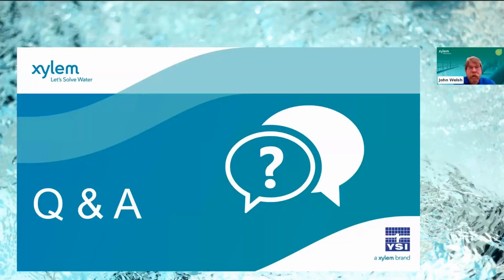We do recommend, however, a yearly PM, and as was the case with its predecessor, if local personnel are properly trained, because the PM requirements are very minimal on the 9220, just as they were with the 9210P. So if someone on site could be trained to perform the maintenance, then yes, that could be done in-house.